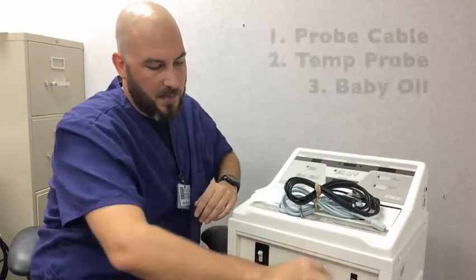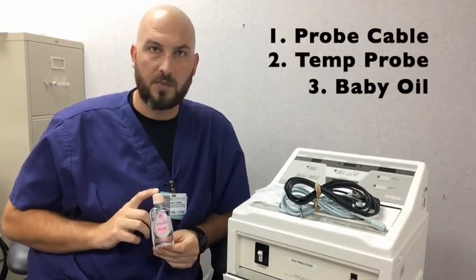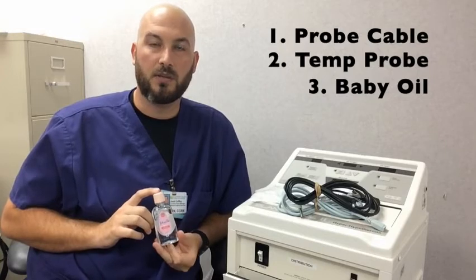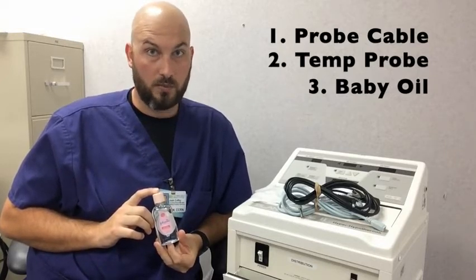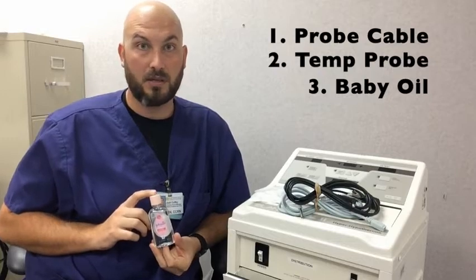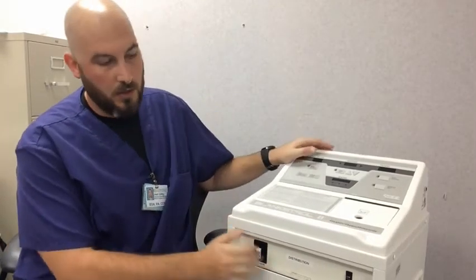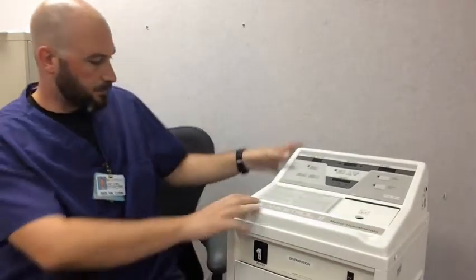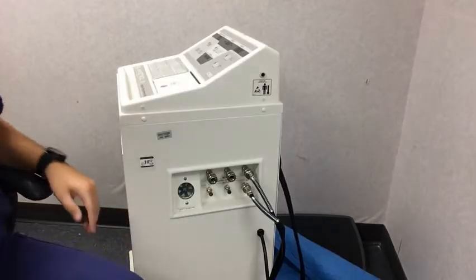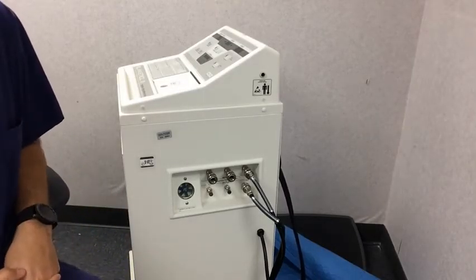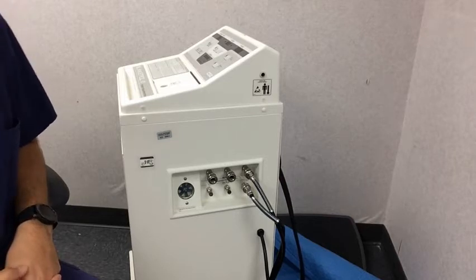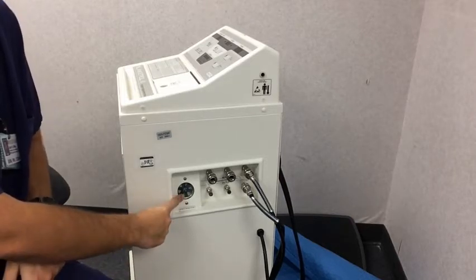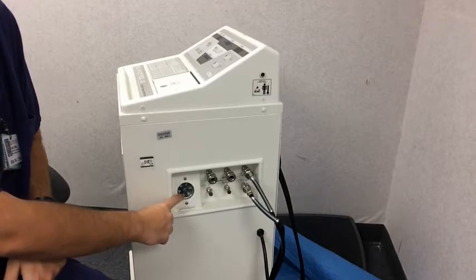And the third thing is a bottle of baby oil. The purpose of the baby oil is to create a barrier between the patient's skin and the actual cooling blanket to assist in preventing cold injuries. For the machine itself, you have a toggle switch on the front for on and off. You also have a toggle switch on the front to go between Celsius and Fahrenheit. Moving along the side, you have quick couplings to set up and connect the cooling blanket itself to the machine, as well as an indicator to indicate forward water movement.